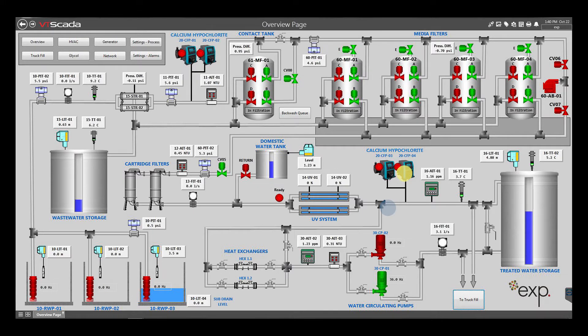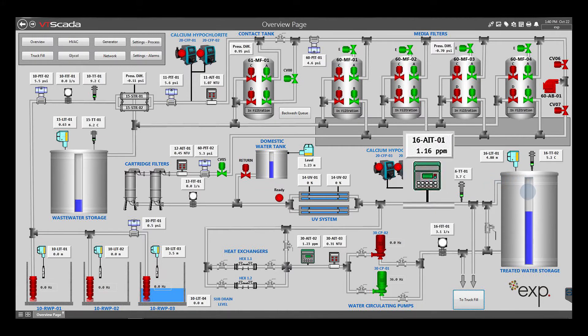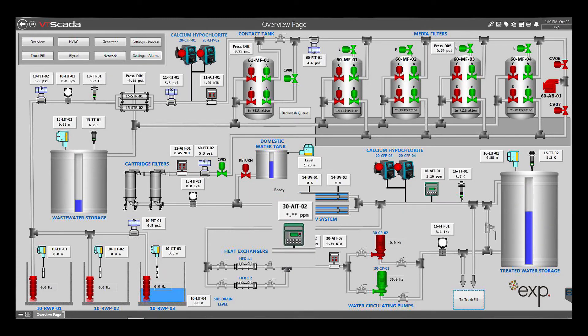Final disinfection happens with a small amount — 1 to 2 parts per million of chlorine — before treated water is sent to the treated water storage tank. The chlorine in the treated water going into the tank is measured by chlorine analyzer 16-AIT-01. The chlorine on the outlet is measured by chlorine analyzer 30-AIT-02.